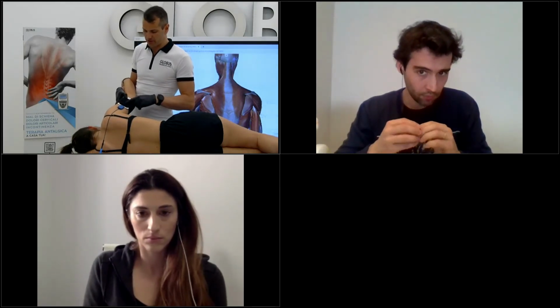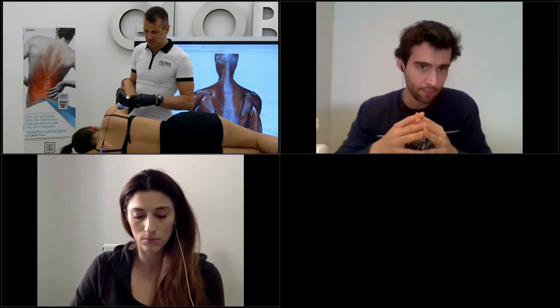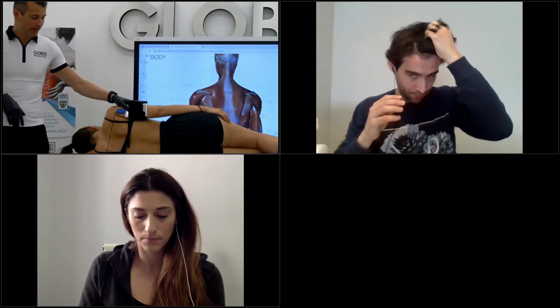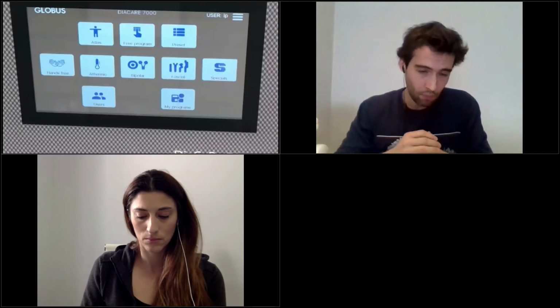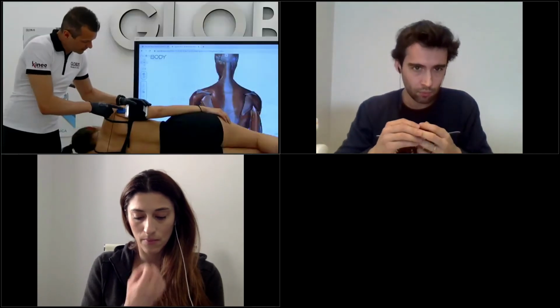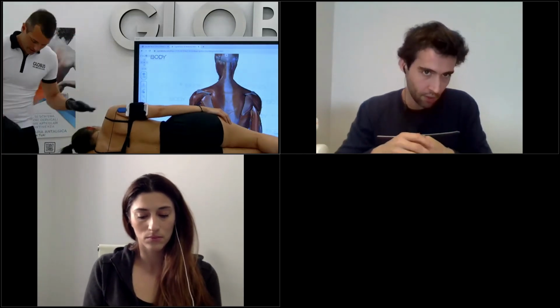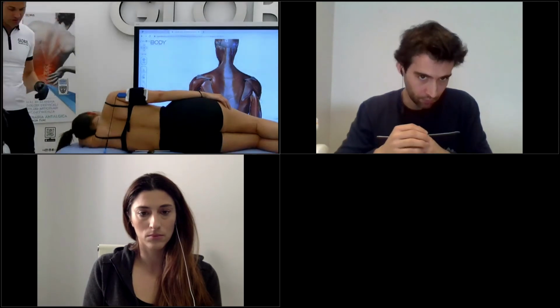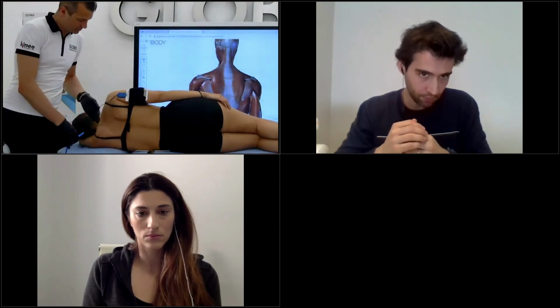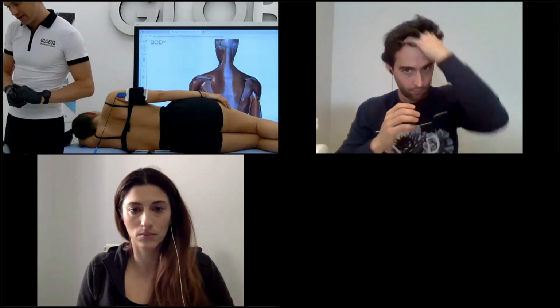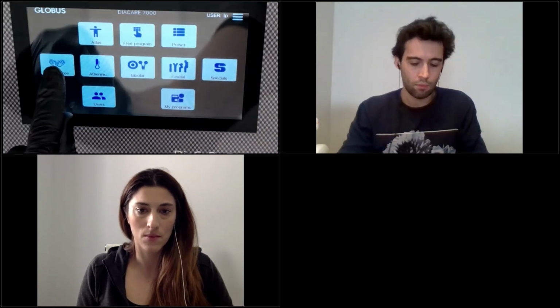Have you seen what I did? I don't know if you're using it, but this is the hands-free. I want to show you on the screen how to set up this kind of treatment. I put the plate under the lateral side, and I put the small plate on the posterior part of the humerus. I could also use the adhesive, but today I decided to use the fixed one, so we can go easily to the hands-free section on the screen. Okay, hands-free.